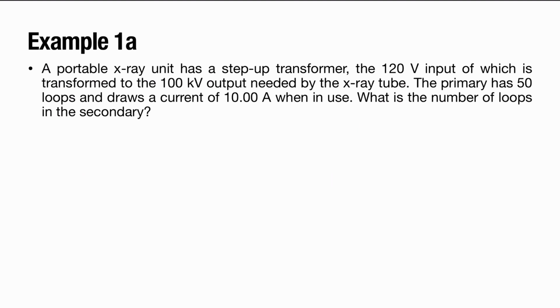Well, here we have a portable X-ray unit in this example, and it has a step-up transformer. This X-ray unit is hooked up to a 120 volt source, but it needs to transform it, or change it, to an amplitude of 100 kilovolts.